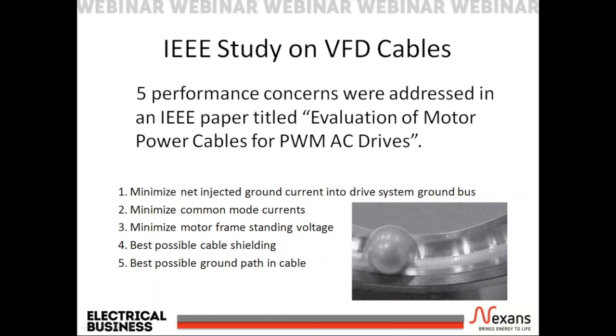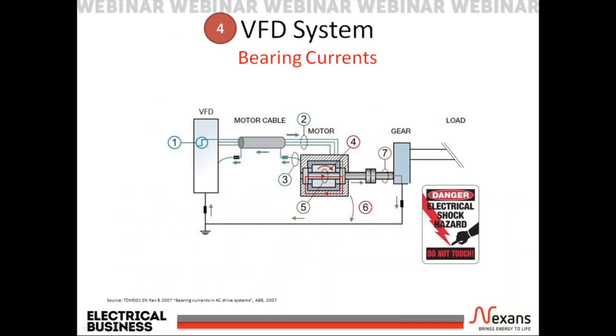Cable shielding will also help to reduce the inductive and capacitive coupling within the system, which can cause induced current or voltage, which could lead to a safety hazard. Number 5, best possible cable ground path. It is critical that there be a long-term, low impedance, wide frequency range ground path from the motor to the drive. In the VFD system, the VFD creates a pulse width modulated waveform, which is sent to the motor by way of the VFD cable.